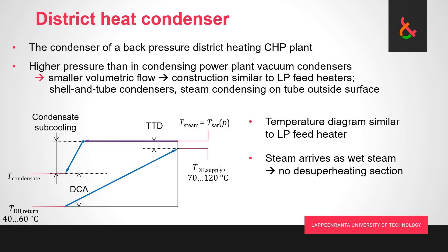One addition in contrast to vacuum condensers is that here we actually do have subcooling marked here. Most of the time we want to operate without subcooling, but we very much want to have the option if we want to. Remember what it does when you subcool condensate in the condenser: it means you are removing more heat from the power cycle.